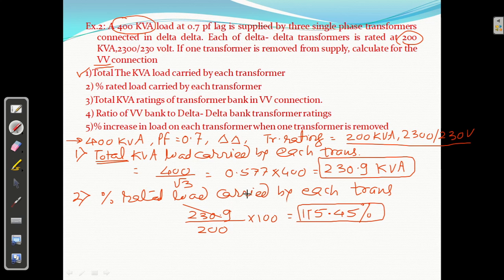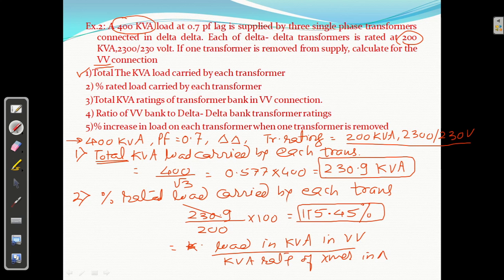So each transformer, the percentage rated load carried by each transformer is percentage rated load, in open delta or VV connection, upon kVA rating per transformer in delta. So you get 230.9 upon 200 into 100, which gives 115.5%. That is the percentage rated load carried by each transformer.